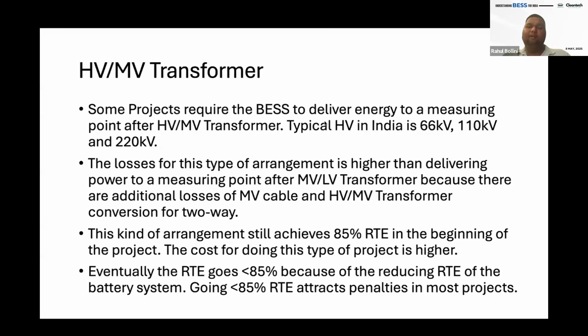So there the round trip efficiency is typically 87 plus, almost 88, but here it's typically below 87. As one would be aware, battery round trip efficiency goes down with aging, and there is a certain risk of RTE dropping below 85 if you're doing this kind of project. Typically depends on use conditions, but in the 6th or 7th year you could see the RTE going down below 85. So be ready to calculate the penalty charges you would be paying for this kind of project.